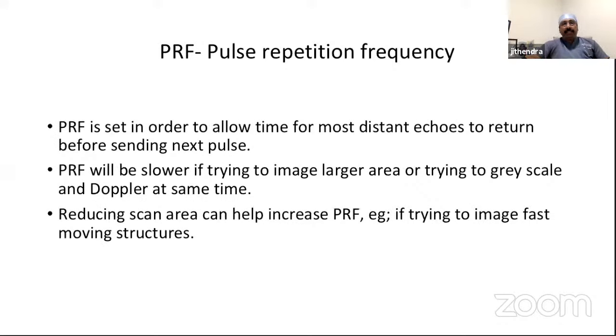Now, pulse repetition frequency is set in order to allow time for the most distant echoes to return before sending the next signal, the next impulse. So pulse repetition frequency will be slower if trying to image a larger area or trying to do grayscale and Doppler at the same time. And reducing scan area can help increase the pulse repetition frequency, for example, if you're trying to image fast-moving structures.